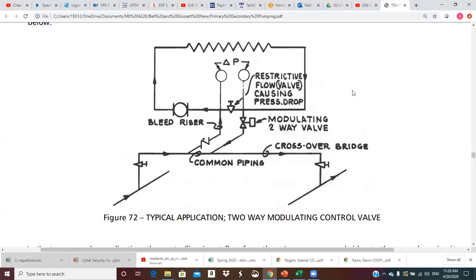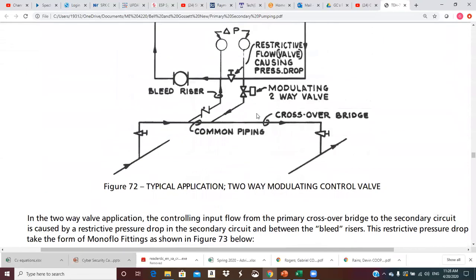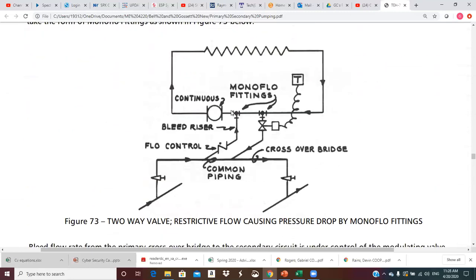Instead of an actual balance valve, Bell and Gossett makes what they call Monoflo fittings that accomplish this pressure drop. Their picture shows these Monoflo fittings, and what those fittings do is described in this diagram — those two fittings equal this balance valve arrangement. They may show it one way or another way in different diagrams.